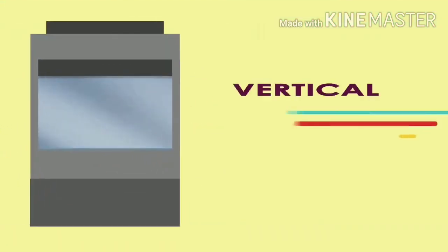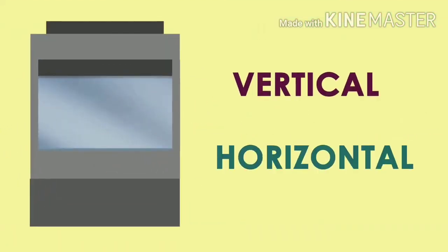There are two kinds of laminar airflow hood, the horizontal and vertical. Air passes through a pre-filter which is 95% efficient to the blower with positive pressure, and to the HEPA filter which is 99.97% efficient.